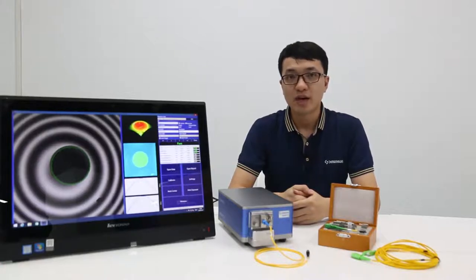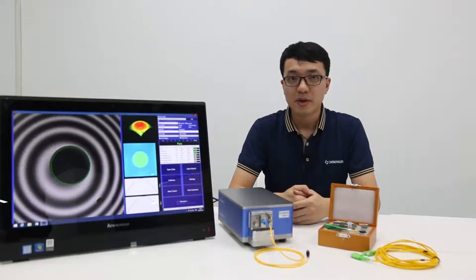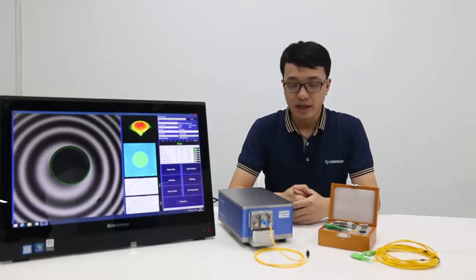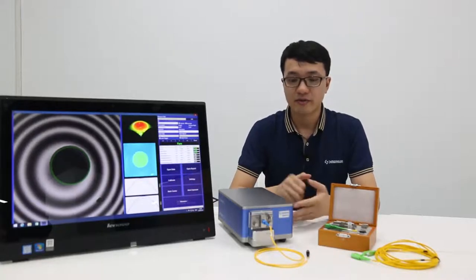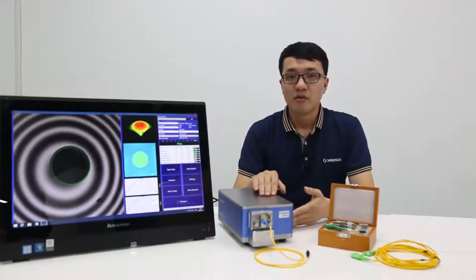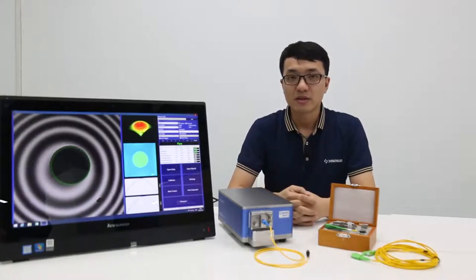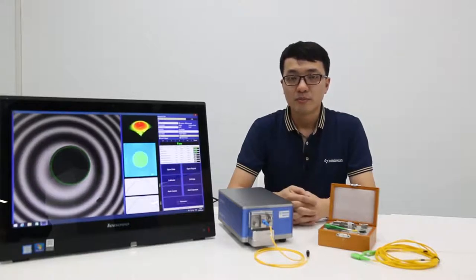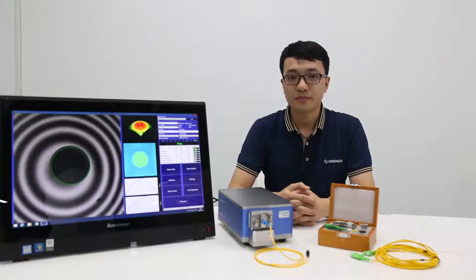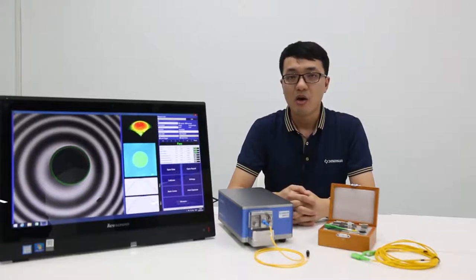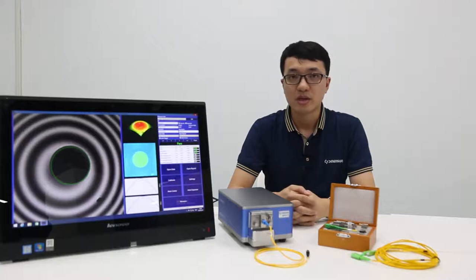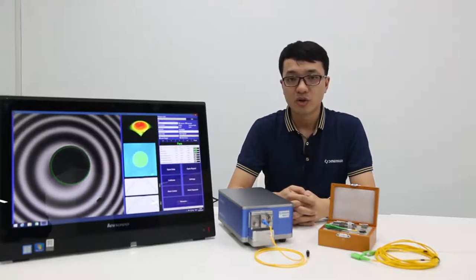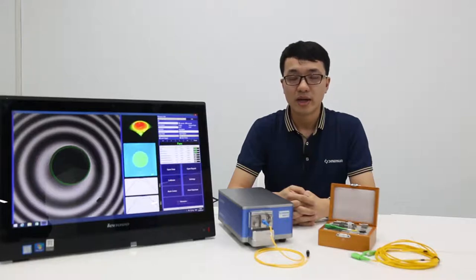BIN-A2 interferometer has some remarkable features including it can handle the fiber height range from minus 1000 nanometer to 1000 nanometer. It has autofocus, auto calibration, auto centering, APC angle auto adjustment, and one quick measurement.